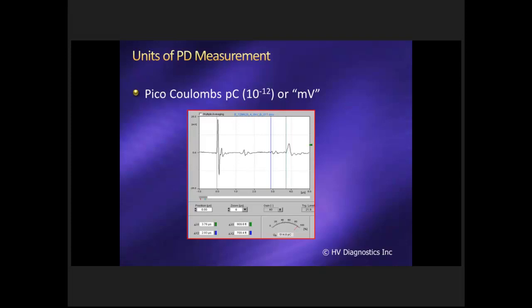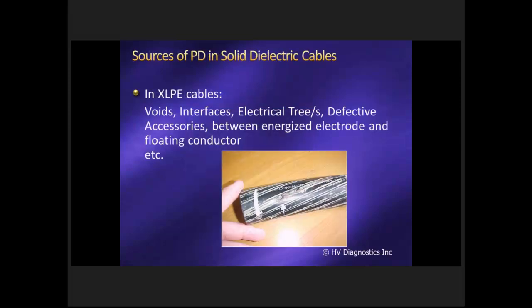So it's quite remarkable that you can actually detect something like this in the field, which has really only come about in the last 10, 15 years. Sources of PD in solid dielectric cables like XLPE, I've listed a few here. Void interfaces, if you have a gap between interfaces, so between a joint body and a cable. Electrical trees, defective accessories, an energized electrode and a floating conductor.